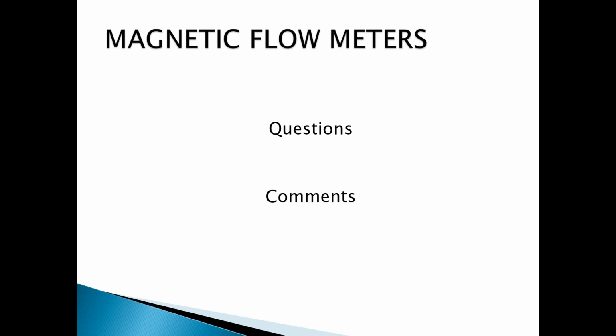And in a lot of cases, for example, we've had some issues where somebody wanted 42-inch grounding rings and they wanted them made out of titanium or tantalum. I mean, obviously the $300 that Norm's talking about, at least in our situation, was the better route to go. But the virtual is there. The other thing I just want to make mention of, it's only available in 3/8 inch size or above, and we need a minimum of 150 microsiemens for the virtual reference to work properly. Right, so you do need a higher conductivity. I'd forgotten to mention that.